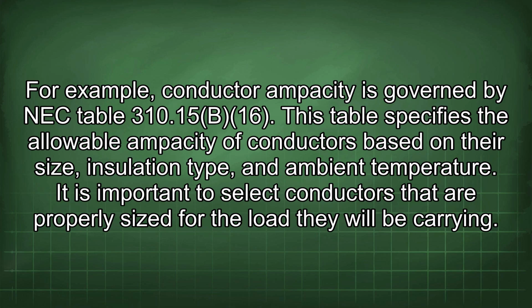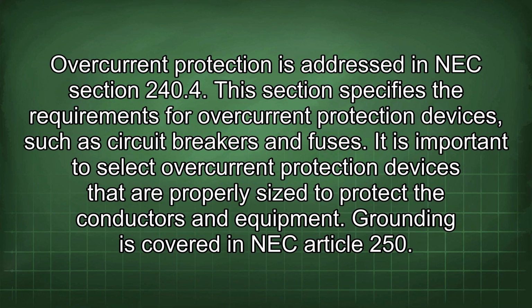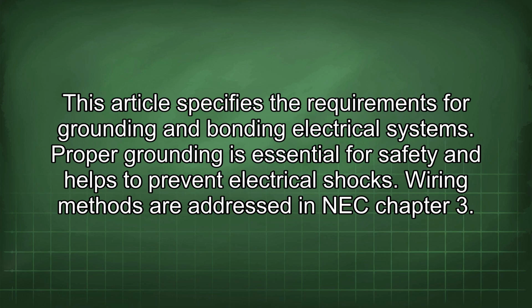It is important to select conductors that are properly sized for the load they will be carrying. Overcurrent protection is addressed in NEC Section 240.4. This section specifies the requirements for overcurrent protection devices such as circuit breakers and fuses. It is important to select overcurrent protection devices that are properly sized to protect the conductors and equipment. Grounding is covered in NEC Article 250. This article specifies the requirements for grounding and bonding electrical systems. Proper grounding is essential for safety and helps to prevent electrical shocks.